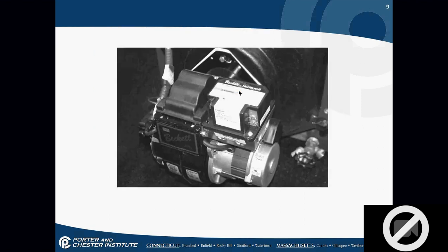This burner, does it have a traditional non-solid state, or does it have a solid state on it? Solid state. You see, it's a little bit of a lower profile. It's not one of those big square boxy looking things. So this has a solid state transformer on it.